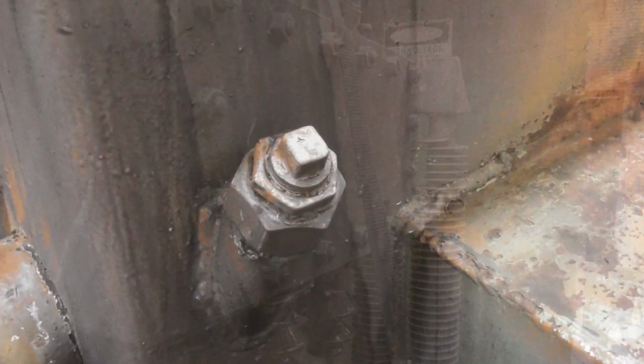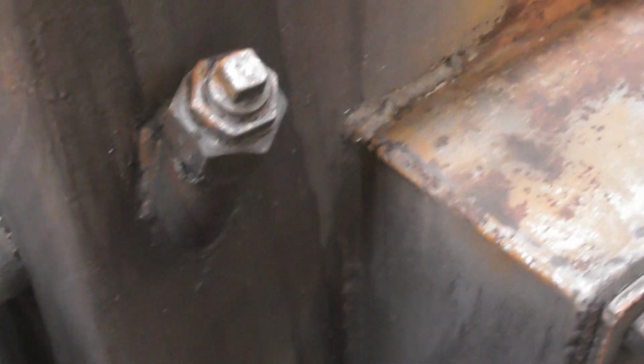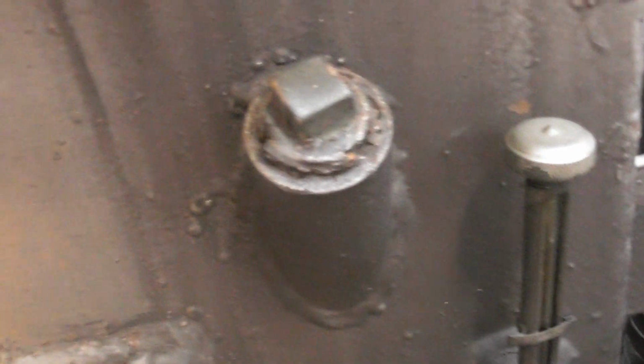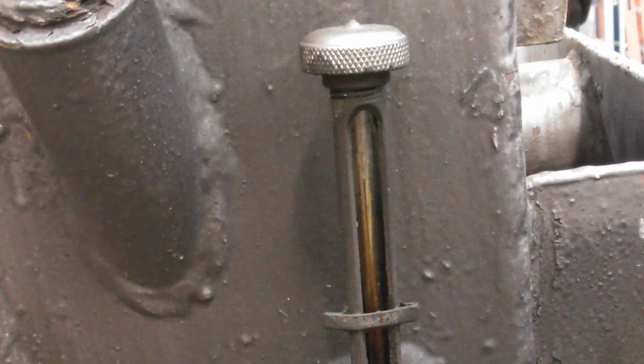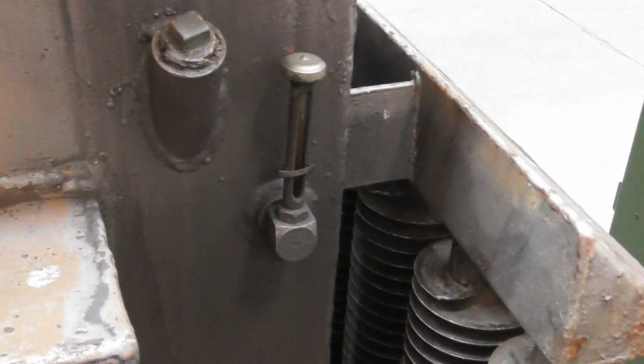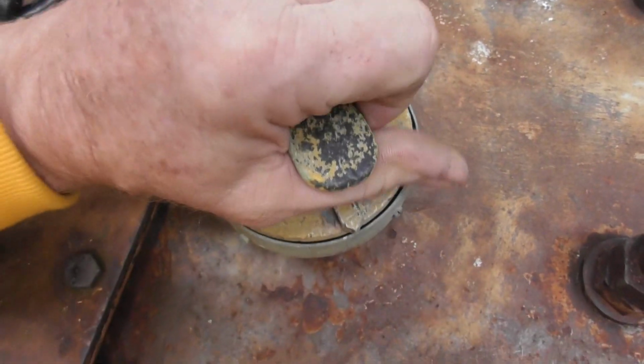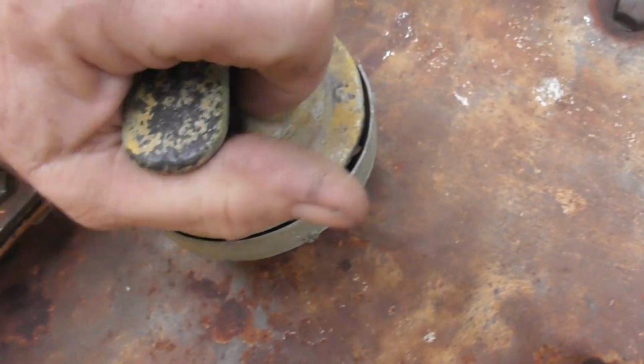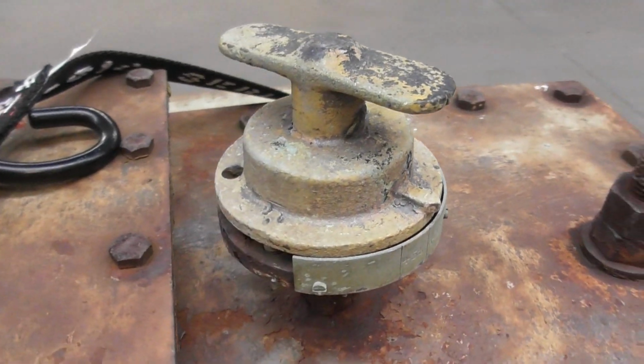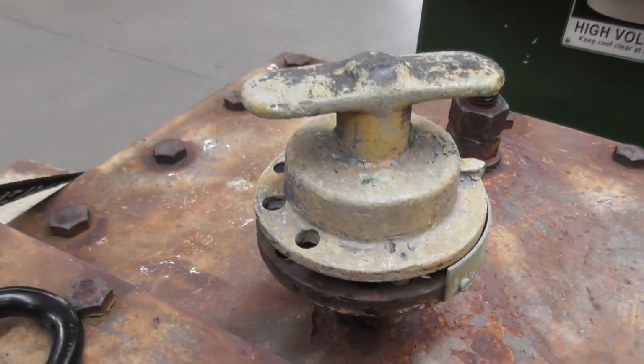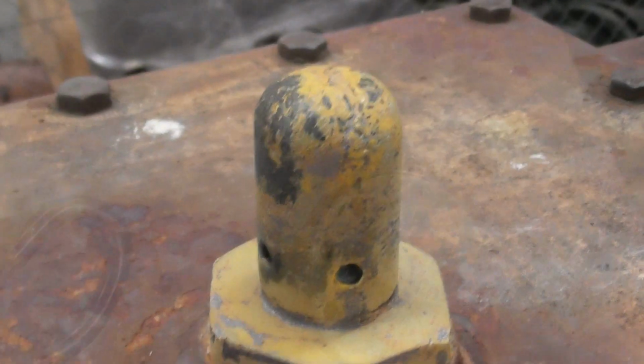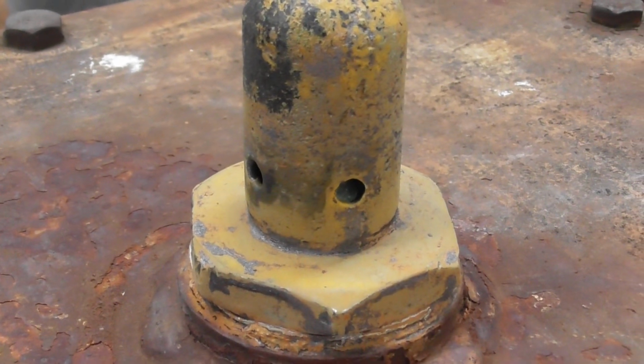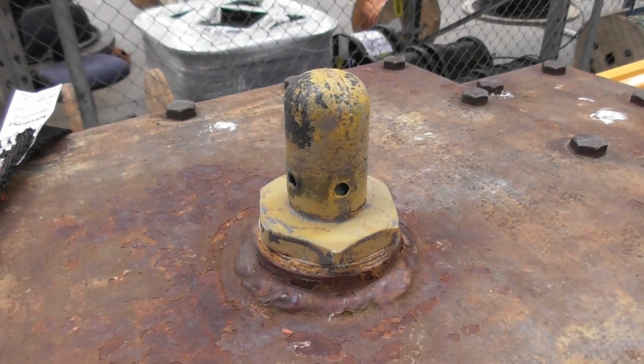Bad idea because this thing will go to the scrapyard unfortunately. Not sure if that's for a temperature gauge you can put in there as optional. Probably is, and here. Oil level gauge. It's just amazing how they make these things. So tap changer, been bolted down I think. Pretty sure you need to pull the thing and then click it to a different position. That will be the breather vent of the device.